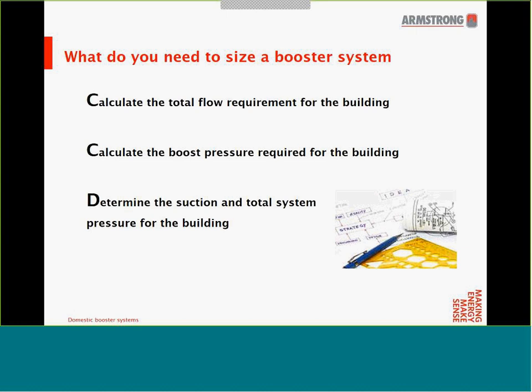To size a booster, like most plumbing systems, there are three important parameters: flow, head, and suction pressure. As it applies to buildings, first we need to determine the total flow that the building requires. We need to determine how much pressure is required from the booster pumps, also known as the boost pressure. And we also need to find out how much pressure is coming from the city or tank into the booster pumps — this is known as the suction pressure.